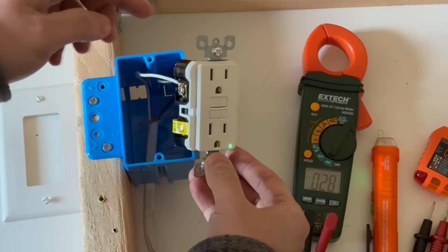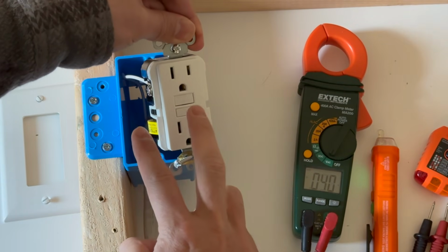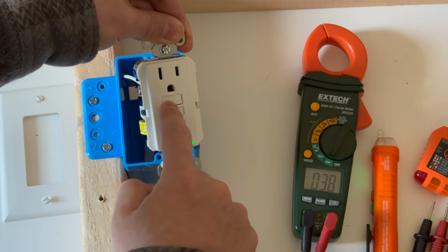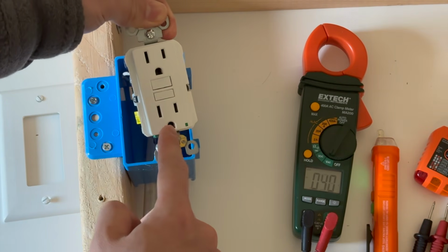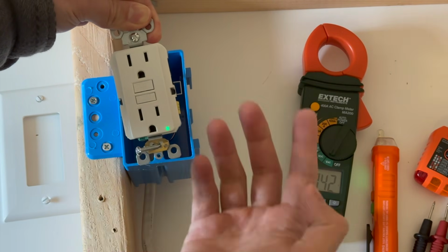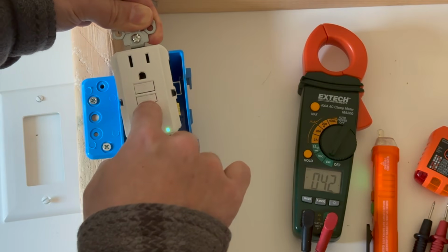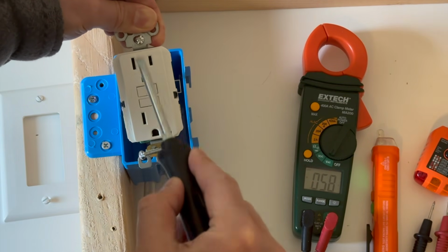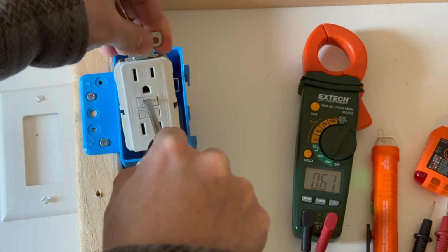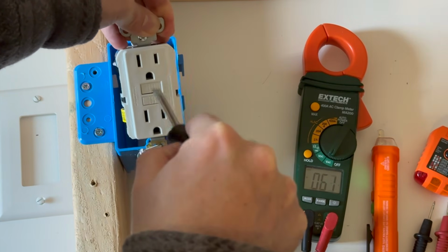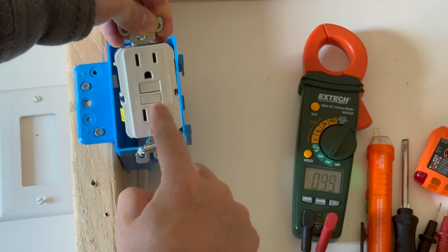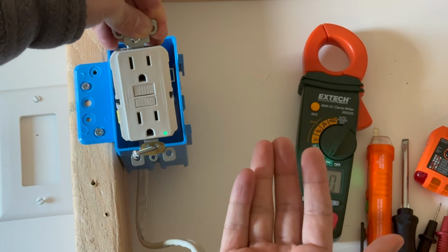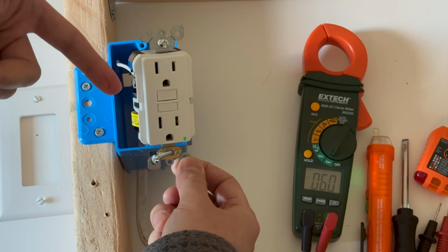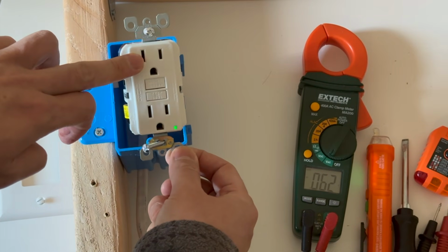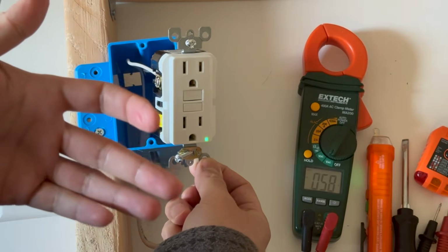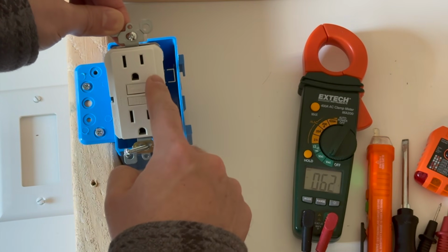Now there's another case where you read the leads, you have a power, but you're not able to reset. You can tell sometimes it just blinks red, or this light, if you don't have it, that's okay. Sometimes you just try to reset it, it pops, but you're not even able to reset it, or you're not even able to test it. In that case, the outlet itself may go out. Okay, so that could be another case. Let's say you have only 2 wires coming to the outlet, which means the power is feeding only this outlet, and you're not able to reset, but visually there's no short, nothing. It's time to replace the GFI.